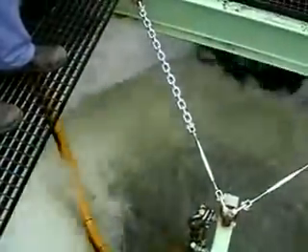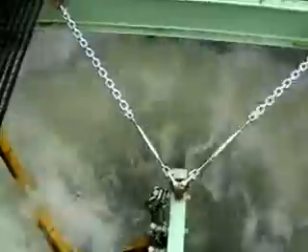It can also result in local vortex type pressure reductions that introduce air cores extending into the pump. This and any other air ingestion can cause reductions in pump flow and fluctuations of impeller load, which in turn results in noise and vibrations leading to physical damage of the pump. Additionally, these fluctuations can impact process loads in other parts of the system. Are there any other special requirements for pumping wastewater?